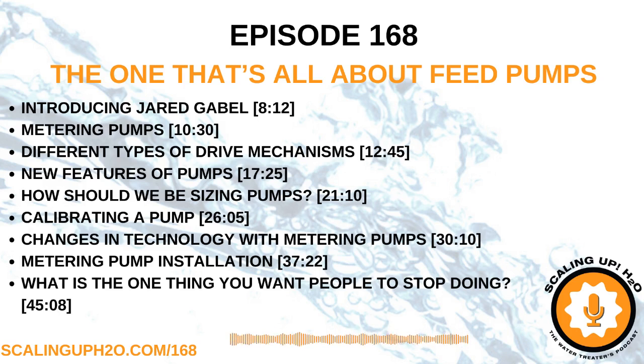And one of the weird things I've seen is where there was a tank in a room above and the skids were on the downstairs level. There was a 3/4 inch pipe coming down to feed two large skid systems. These are pumps that require 1 inch to 1.25 inch suction on each pump, but there was this 3/4 inch pipe coming down and then teed off to both skids. I had one skid on and running, and then I heard the dosing skid and the pumps, I heard the check valves chattering. That means it was actually hydraulically impacting the skid that was off. And that was just not a good scenario.